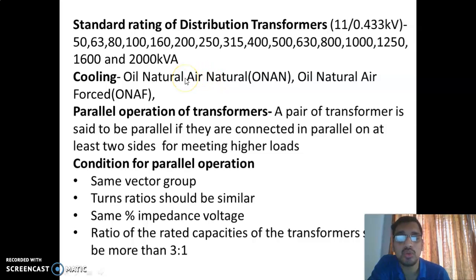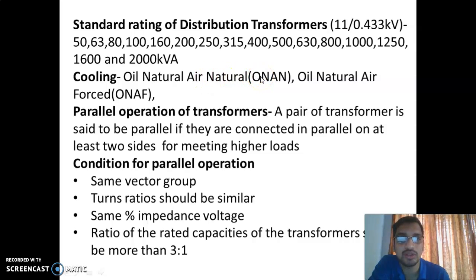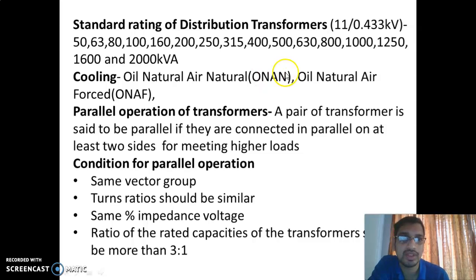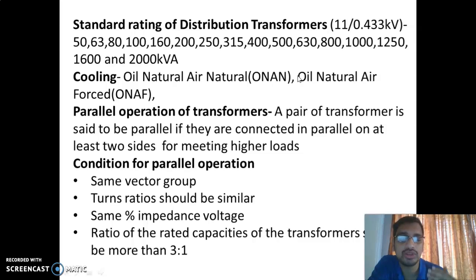There are two types of cooling in a transformer. One is Oil Natural Air Natural (ONAN) — for small type transformers, ONAN is used, where the transformer is cooled with oil and air naturally. The next type is Oil Natural Air Forced (ONAF), where a blower or fan is used to increase the flow of air, so oil cooling is natural but the air is forced.